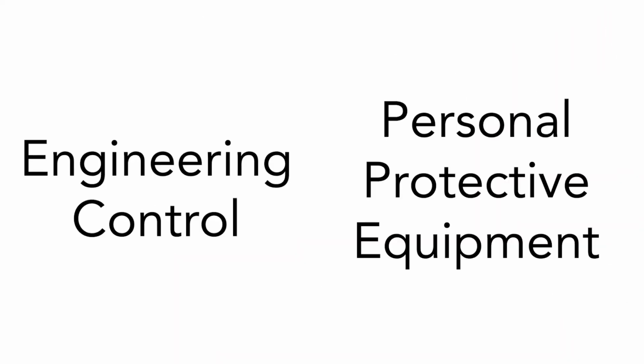In the simplest of terms, when a fume hood is working properly, there is no loss of containment. Loss of containment exposes the user to various hazards. This is why the fume hood also belongs in another class of products called exposure control devices. Much confusion comes from the fact that the fume hood is a hybrid device. Not only is it part of a complex mechanical ventilation system, it is also a PPE designed to protect the user from various hazards. This hybrid classification is the source of a lot of misunderstanding.